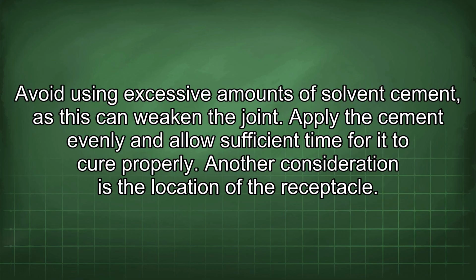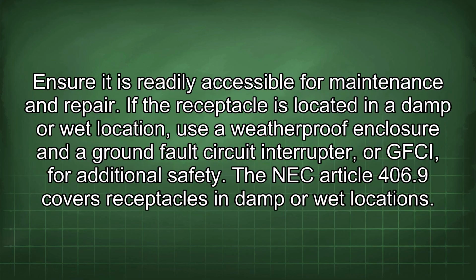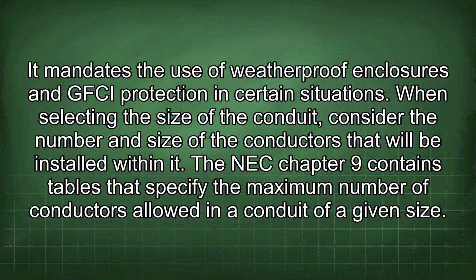Another consideration is the location of the receptacle. Ensure it is readily accessible for maintenance and repair. If the receptacle is located in a damp or wet location, use a weatherproof enclosure and a ground fault circuit interrupter, or GFCI, for additional safety. The NEC Article 406.9 covers receptacles in damp or wet locations. It mandates the use of weatherproof enclosures and GFCI protection in certain situations.